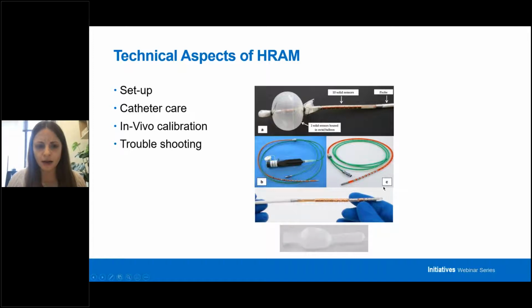I've got a few different brands of anorectal manometry catheters. These catheters have a number of channels and sensors, usually around 4 to 5 millimeters in diameter, so they're very thin. There's a balloon at the tip of the catheter, and also a balloon shown by itself in the bottom image. The balloon is deflated during insertion, but then inflated as part of the test to detect rectal sensitivity. Sensors here test anal sphincter strength, while sensors inside the balloon test rectal pressures.